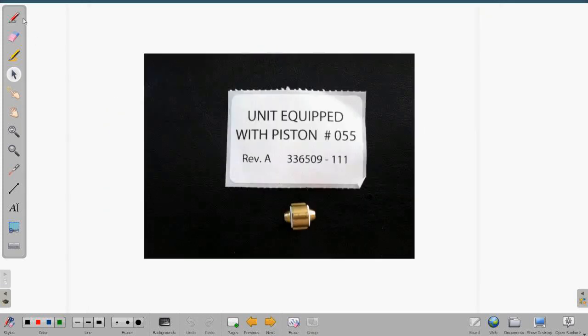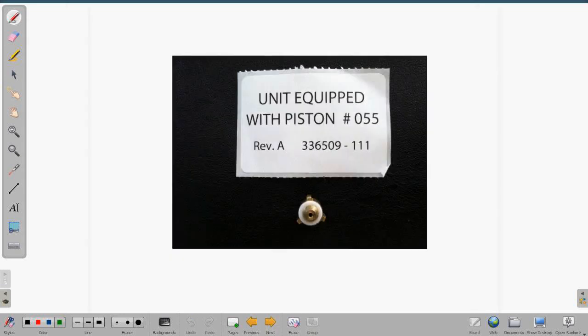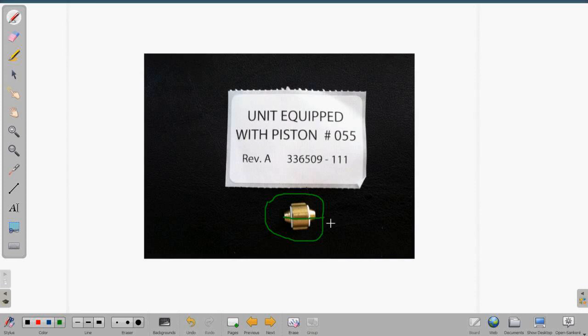So this is the piston metering type device. It's very simple, pretty bulletproof. It's been used for quite a few years, and little if anything can go wrong with it. So that sits in a receiver right in front of the evaporator coil. And then the top view is right here, and this is where the refrigerant gets metered down and the pressure is dropped through the piston. So basically, it's just a straight through hole, and there are different piston sizes for different tonnages of equipment. But we're not going to get into that, but the manufacturer's specifications will have that for you.